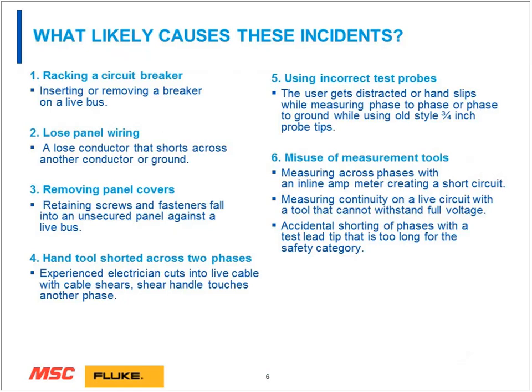What likely causes them? First of all, racking a circuit breaker, especially if it's on a live bus. If you're not working on a de-energized panel and you're doing live testing, which you need certain authority to do within your organization, racking that circuit breaker could cause something. Dust, any type of metal debris, filings from any of the stranded conductors. Anything can happen, especially when you're disrupting it. Loose panel wiring, where it breaks loose and actually comes down and shorts across another conductor.